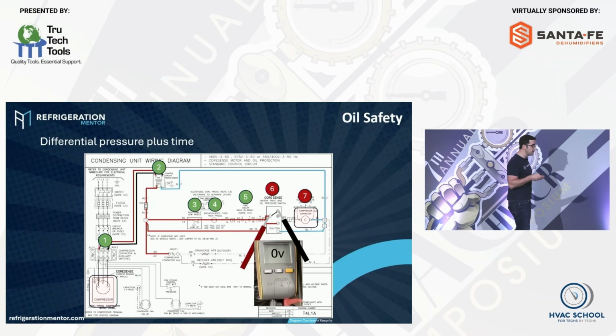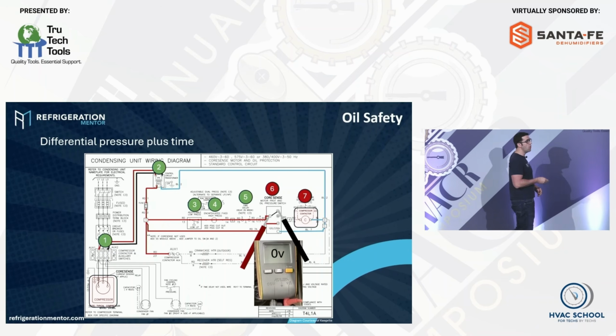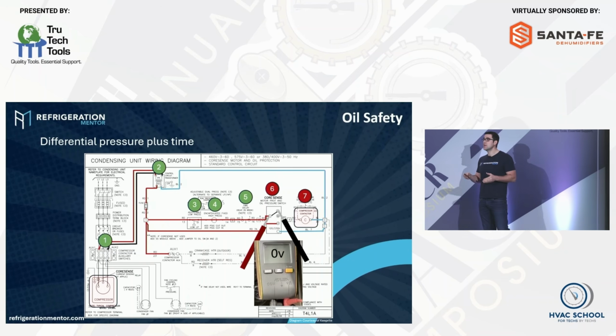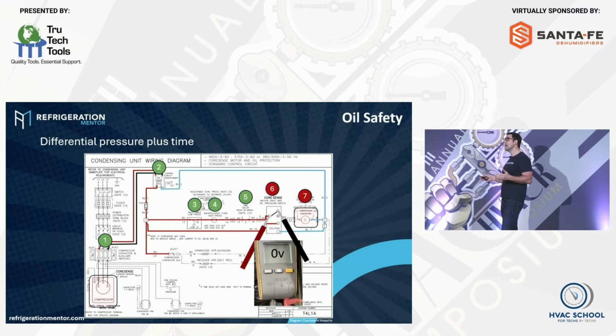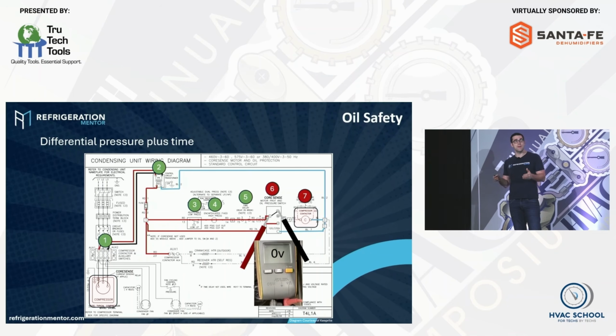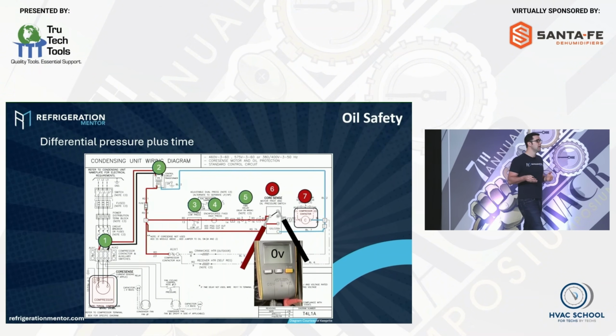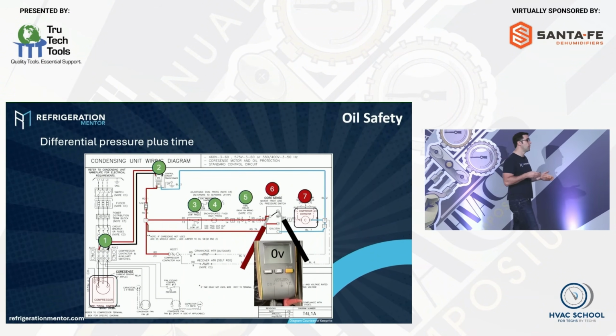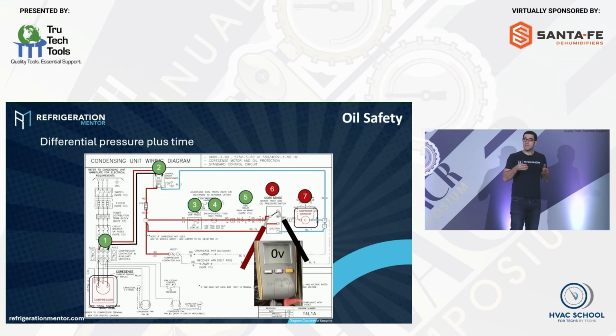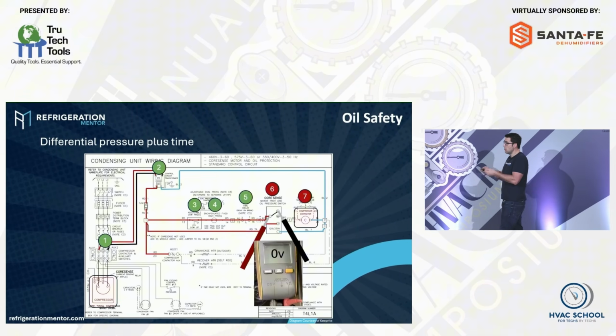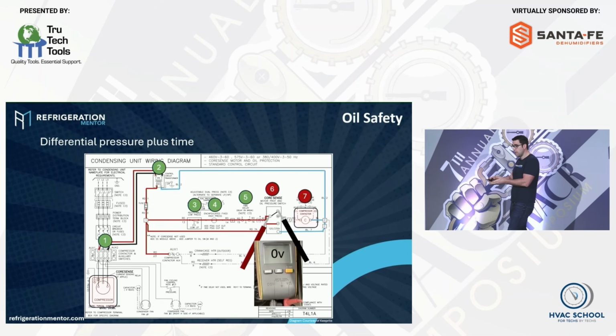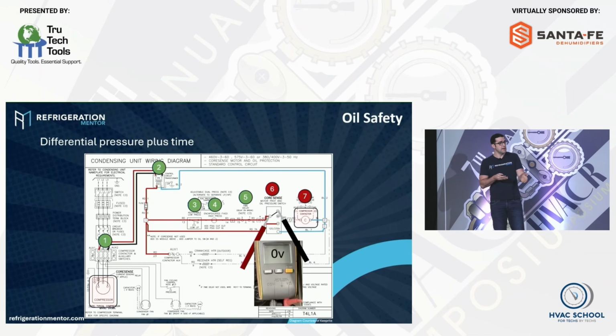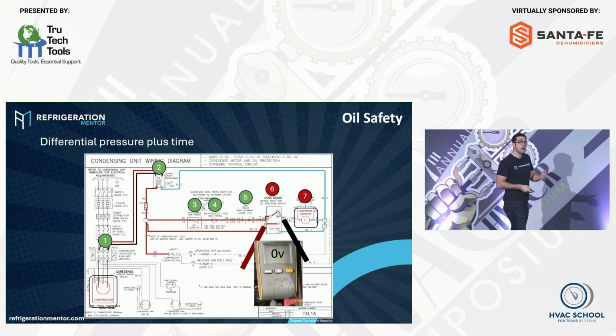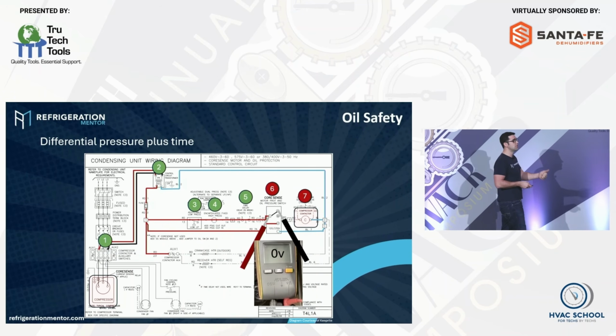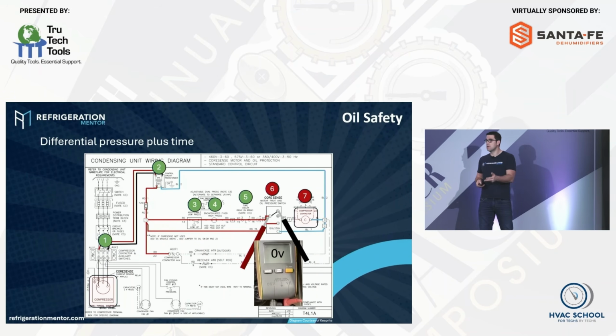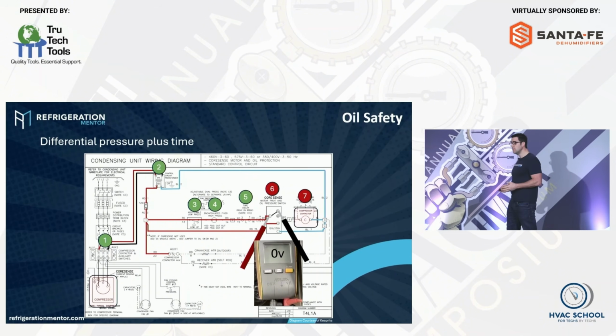Oil safety. This is one of the big things in refrigeration if you have oil safety sensors. Differential pressure plus time. What does that mean? That means that I trip out at 7 to 9 PSID or 0.6 BARD. What does that mean? So I tripped, I look at it, oh, my pressure differential is too low, but it still hasn't tripped the unit yet. Now there's a time delay, a 90-second or a 120-second delay in your Sentronics or your Delta P's or your Penn or your Danfoss oil safety controls.